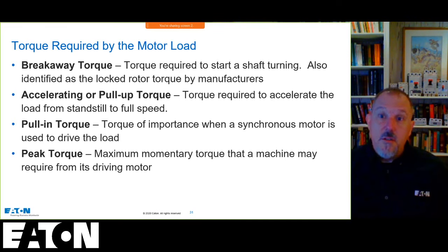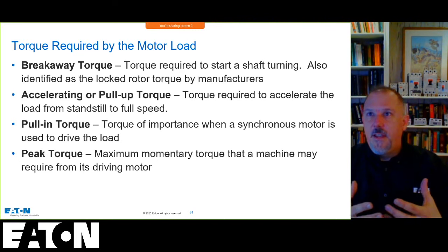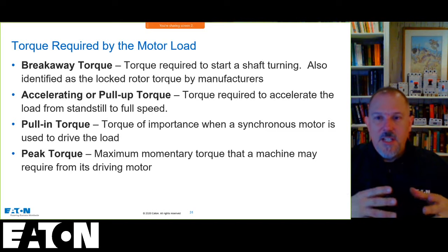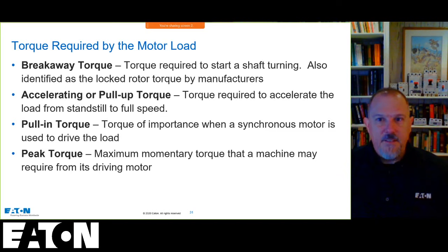Accelerating, or pull-up torque. So this tells you, if I have a conveyor belt, and I use a conveyor belt because I think I can visualize that, loaded with coal or whatever it is, I'll have the breakaway torque to get that conveyor belt moving. But it'll take me a period of time to get that conveyor belt up to speed, because now I'm moving a weight.